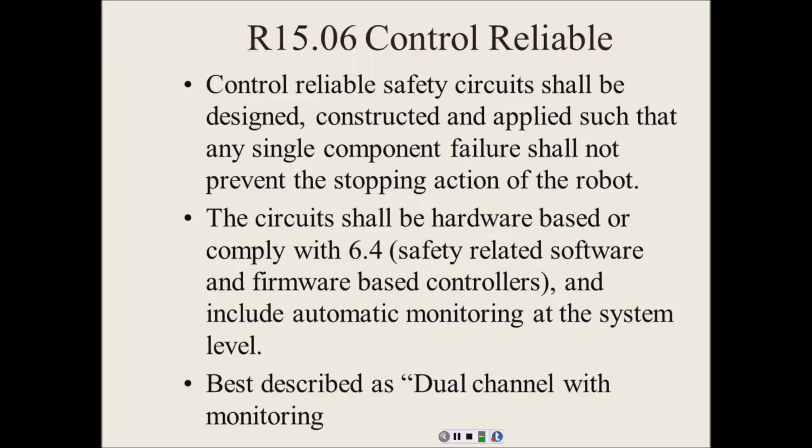The circuit shall be hardware based. So that means even if you do a lot of safety stuff, this guy was talking about ultrasonic sensors and all that kind of stuff. That's great, and these work good, but the safety and e-stop circuits have to be hardware based. You know what hardware is? Y'all been reading those? What is hardware?